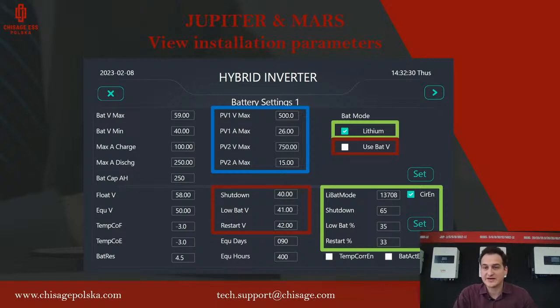But if we use any other battery without communication, like a lead acid battery, we have to fill in this information to make sure the inverter will work correctly with our battery. On the right bottom, we have battery active enable. If we pick this option, the inverter will try to start the battery if it's in shutdown or standby mode. So if the battery gives no voltage, the inverter will try to push some power to the battery to turn it on.